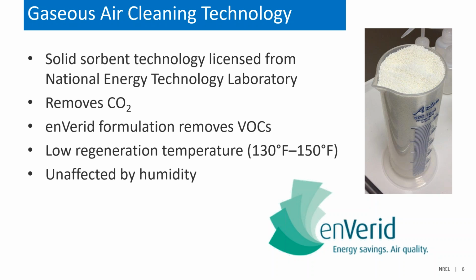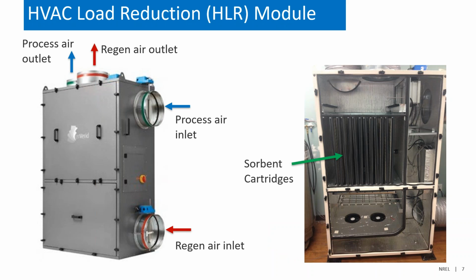So other sorbent materials have very high regeneration temperatures, and humidity tends to reduce the effectiveness of the material. So in this case, the advantage is that it does have that low regeneration temperature and is unaffected by humidity. So what they've done is they take that sorbent material and they put it in these cartridges, and then they put it into this device they call the HVAC load reduction or HLR module. And you can see a picture of one of the versions here.